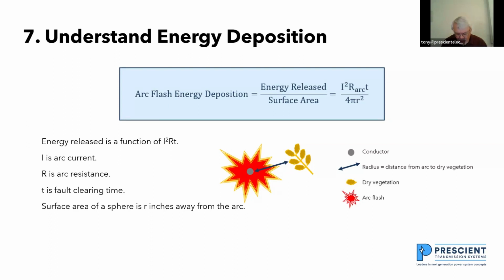Arcs typically have 500 volts per foot. So if you know what the current is, you know what the arc resistance is, and you can calculate the energy that's released as a function of I squared R T. For the surface area, we're assuming that we've got a sphere and the energy is all on the surface of the sphere. We don't lose a lot of energy through air. You notice this at campfires. When you get too hot at a campfire, you back up, and when you're too cold, you get closer. That's the same type of thing we're talking about here.